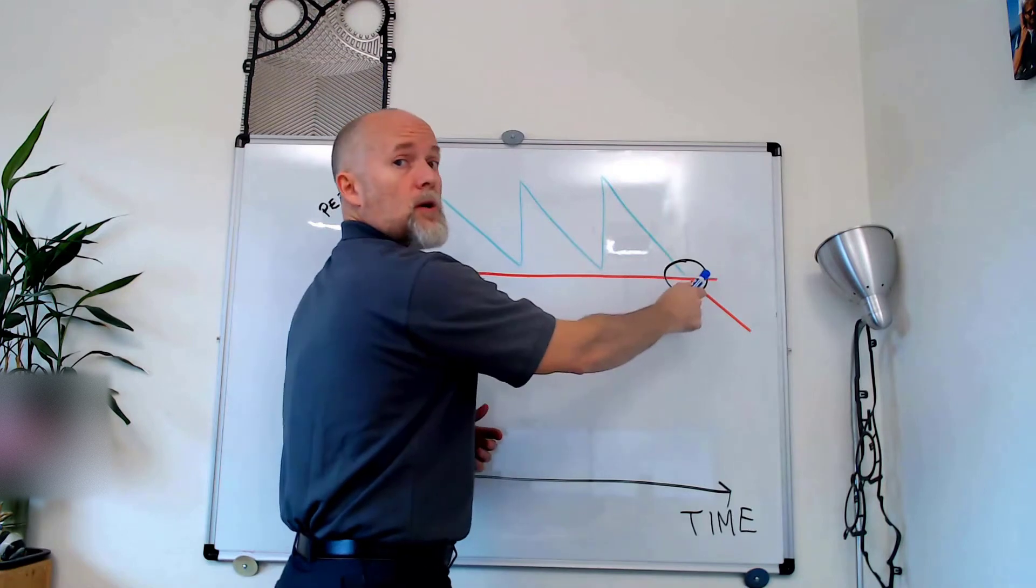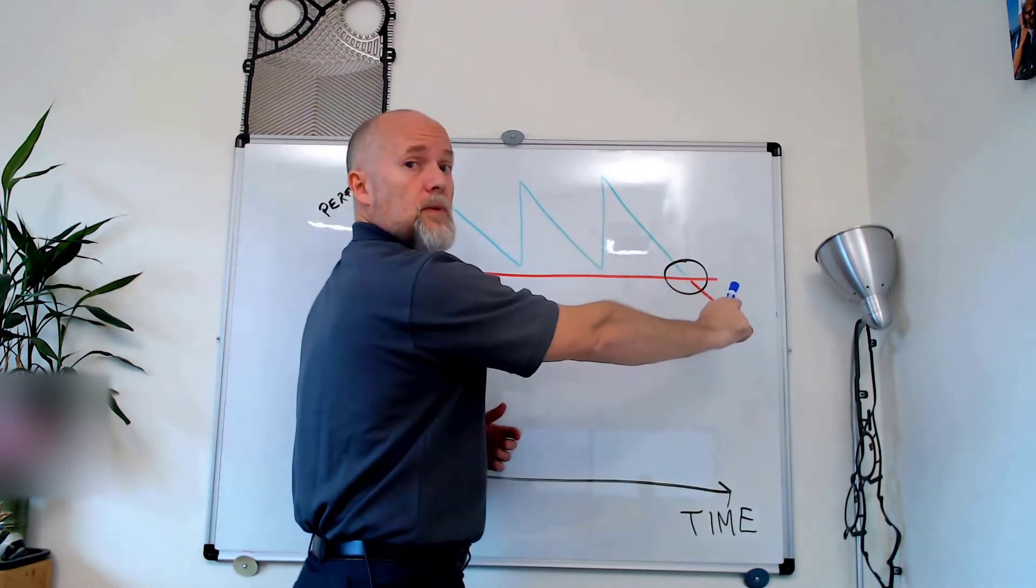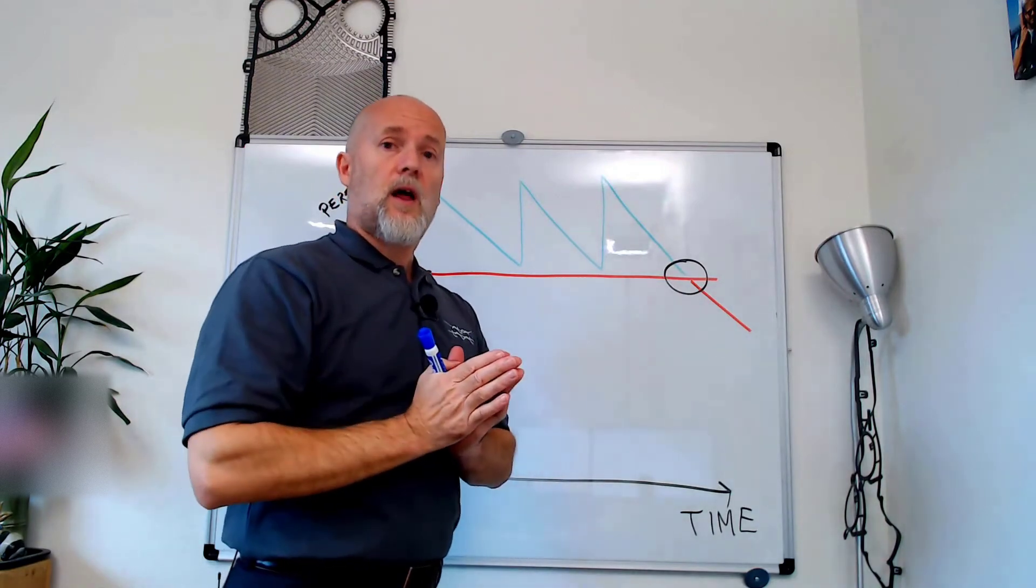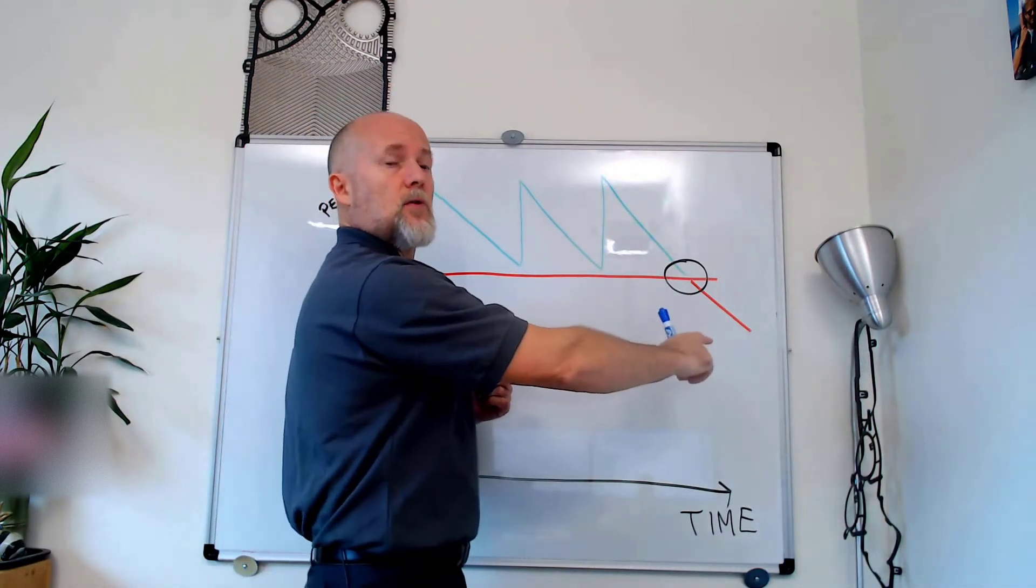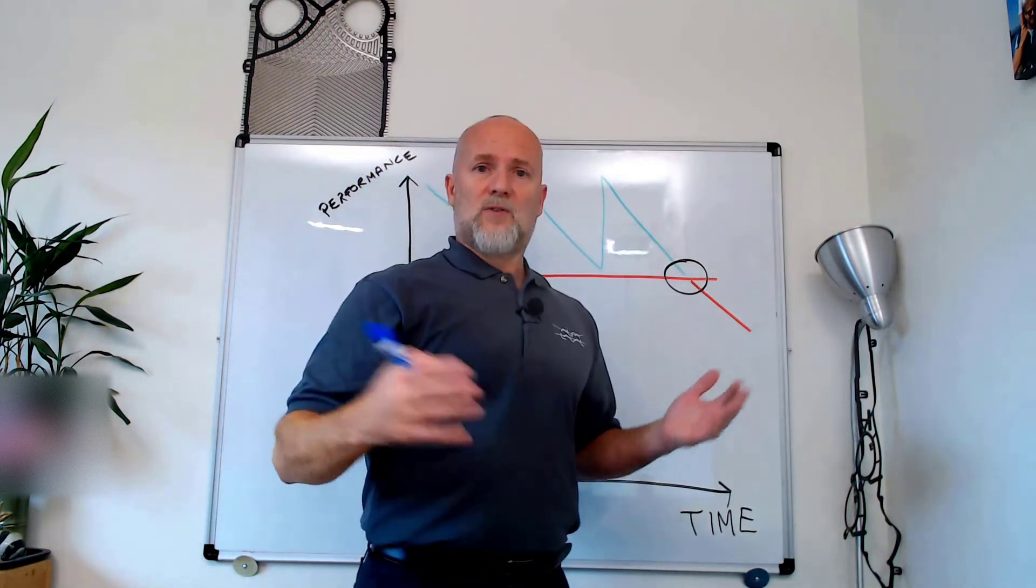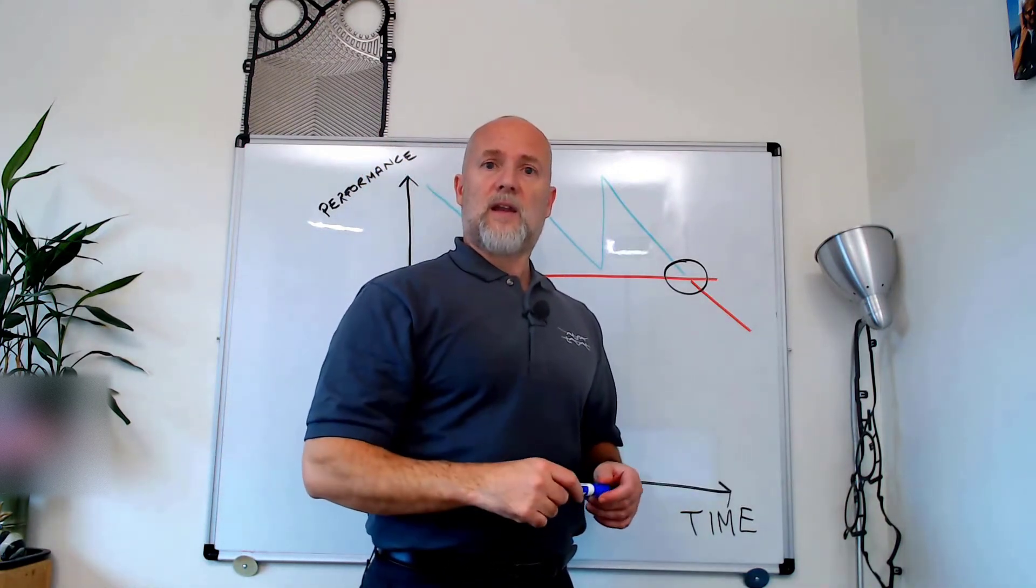Until you reach this point, there's a threshold that you don't want to pass because at that point the channels are clogged and the CIP cycle doesn't work anymore. And at that point the only chance that you have is to mechanically open and clean the plates.